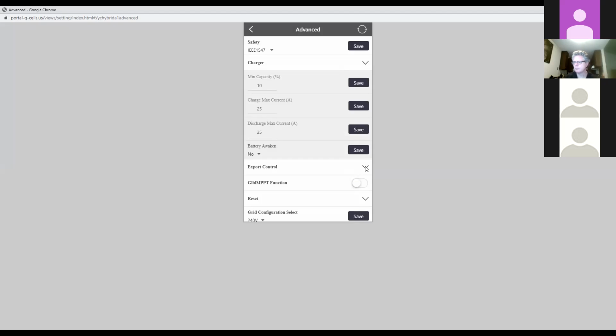You can also control the export - for example, if you don't want to backfeed more than 1 kilowatt to the grid, you can set that number from 0 to 60 kilowatts. This is particularly important for Hawaii, because there we're not supposed to feed back anything, so it has to be 0, and we can do that.